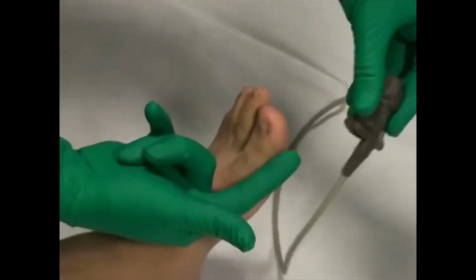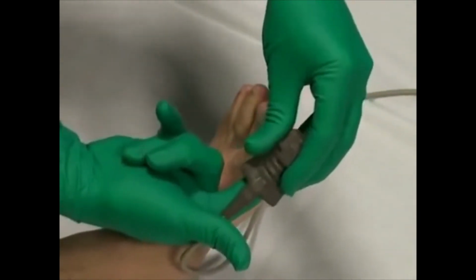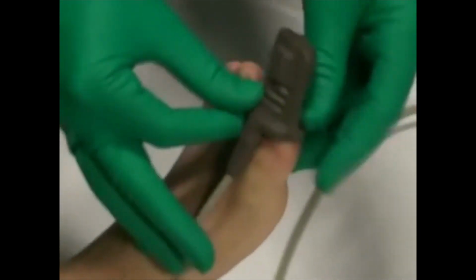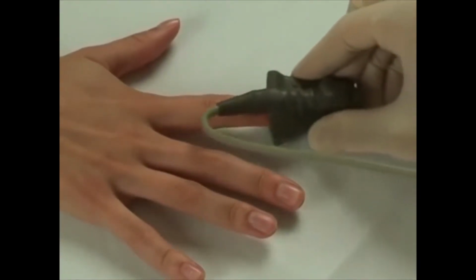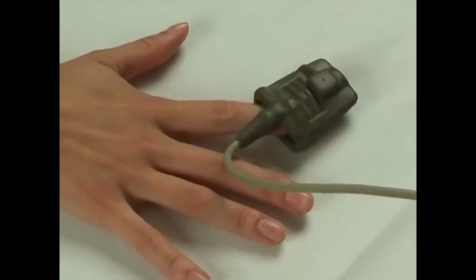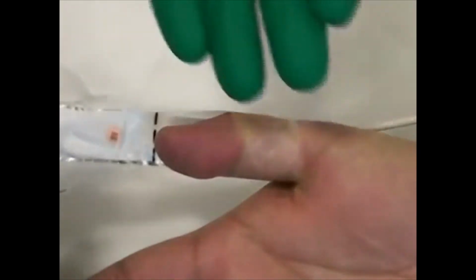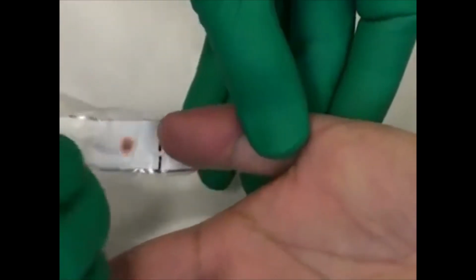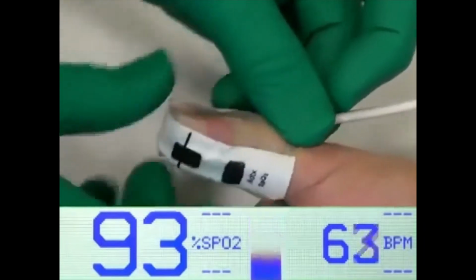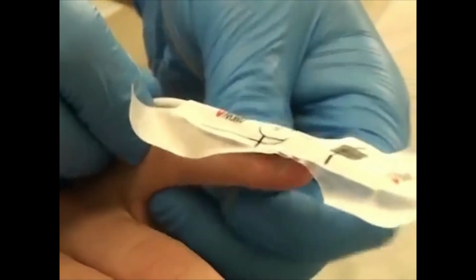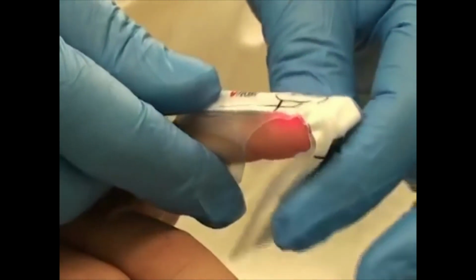It is important to choose a probe that is the right size for the patient. If the probe is not the right size, the light-emitting diodes may not line up correctly with the photodetector and will provide inaccurate data. For example, a probe that is too large for a patient's finger may slip, and the light may not pass completely across the finger. Venous pulsations may occur if a probe is too small or is placed too tightly on the finger. These venous pulsations will produce interference, resulting in a falsely low pulse oximeter reading. Pulse oximeter probes with adhesive sensors may minimize motion and may yield more accurate results than non-adhesive sensors.